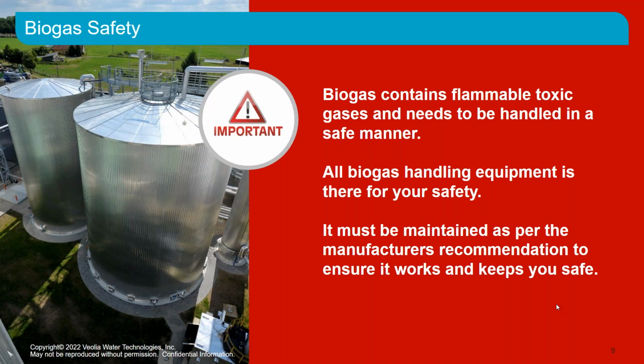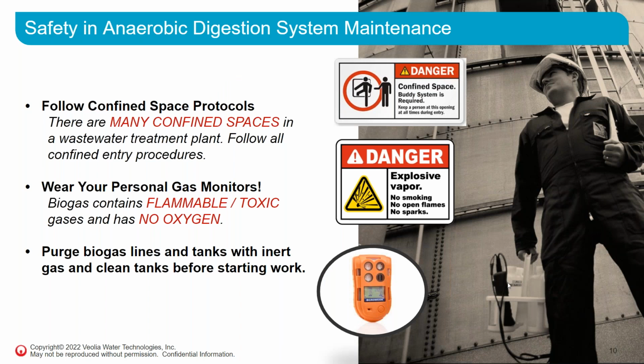So biogas safety, the first topic. As you all know, biogas contains flammable, toxic gases and needs to be handled in a very safe manner. All biogas handling equipment is there for your safety, and it must be maintained as per the manufacturer's recommendation to ensure it works and keeps you safe. Especially when you work in your wastewater treatment facility, you can find a lot of confined spaces, and don't forget that you have to follow all the confined space protocols, especially when you enter the empty tanks.